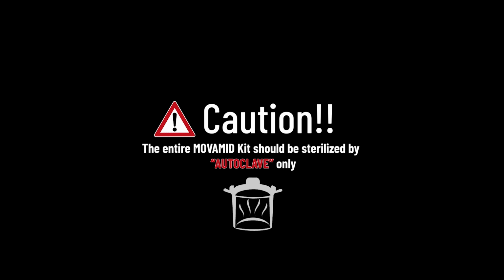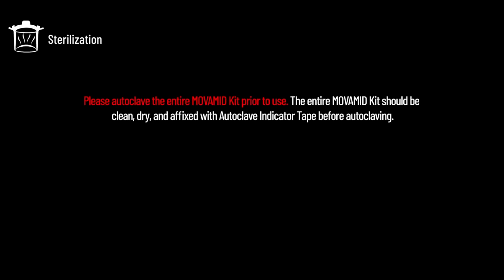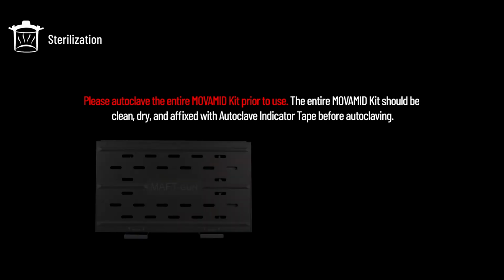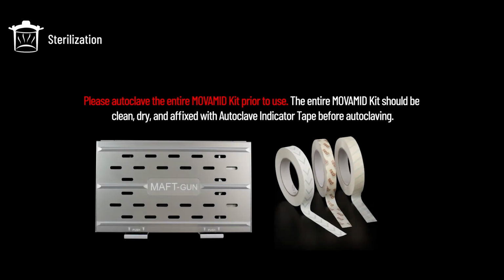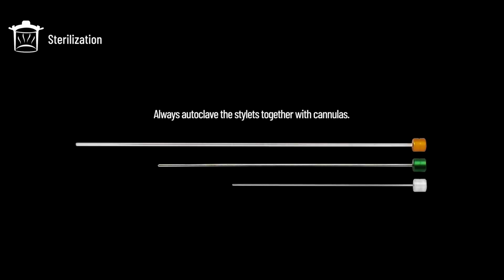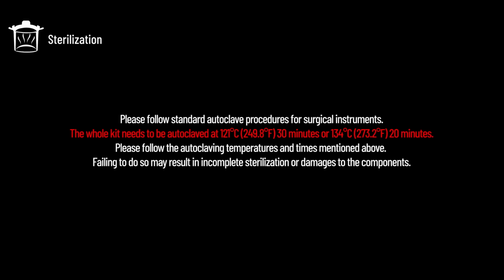About sterilization. Caution. The entire Movamid kit should be sterilized by autoclave only. Please autoclave the entire Movamid kit prior to use. The entire Movamid kit should be clean, dry, and affixed with autoclave indicator tape before autoclaving. Always autoclave the stylets together with cannulas. Please follow standard autoclave procedures for surgical instruments.